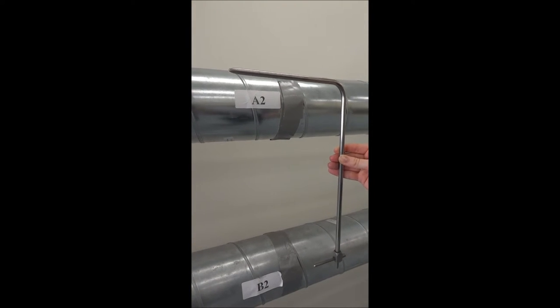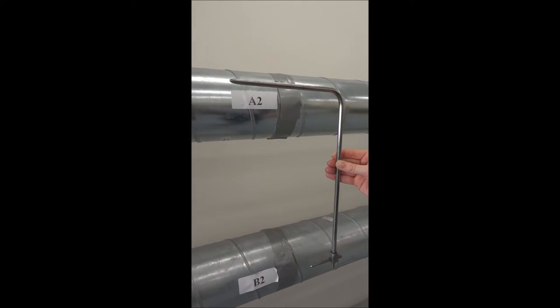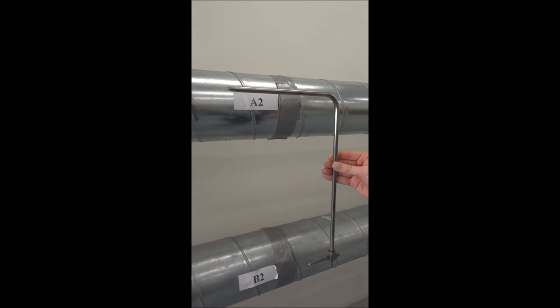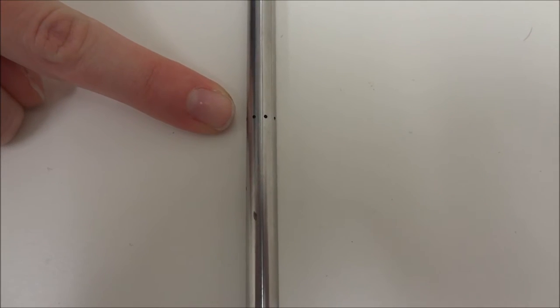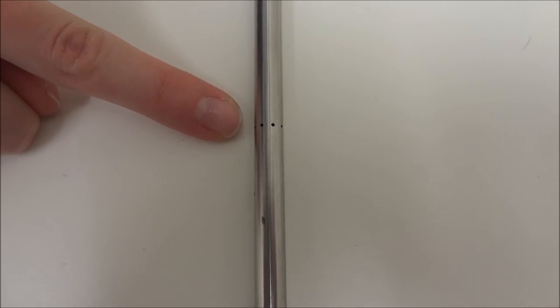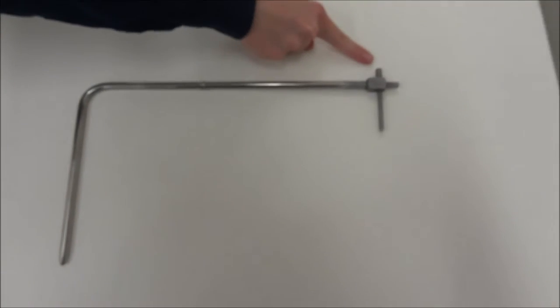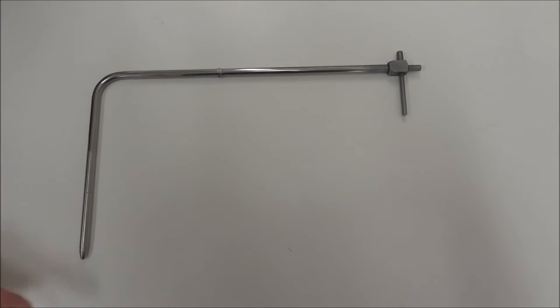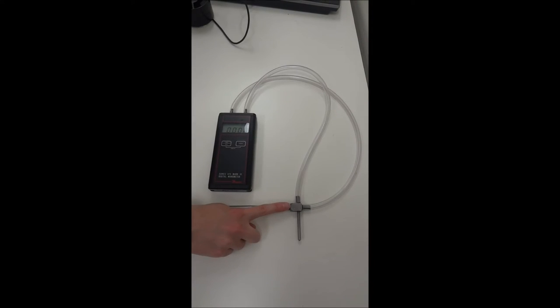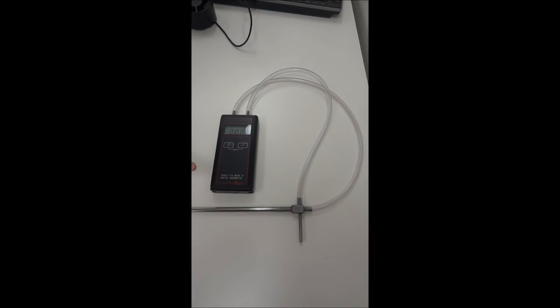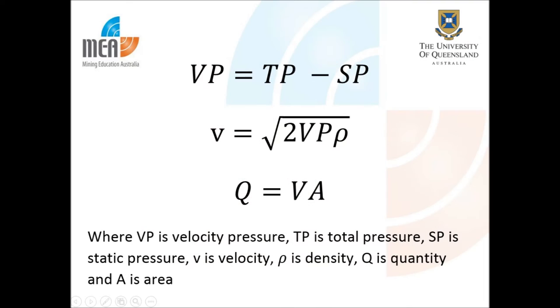This is a pitostatic tube. It sits in the duct like this once inserted, and airflow through the duct is recorded by small sensor holes. These holes around the outside of the tube record the static pressure in the duct, and the readings come from this side outlet here. The inner tube records the total pressure and those pressures are recorded from this straight outlet. Connecting these two outlets to the digital manometer allows the velocity pressure to be displayed on the screen.